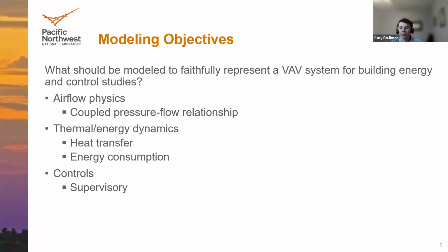So for example, the static pressure set point of the air handling unit or the supply air temperature of the air handling unit. But then you also have local controls, which is more of like what's going on in terms of how these components, like dampers or coil valves, are being actuated to meet the desired set points. And then connected with that is the actuation, how we can model the movement of valves and dampers and things like that, which sort of connects the controls back to these physics.